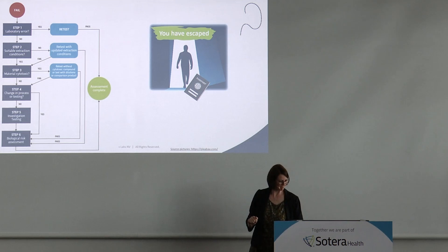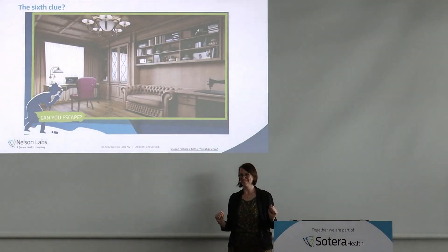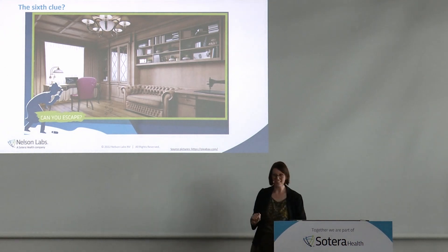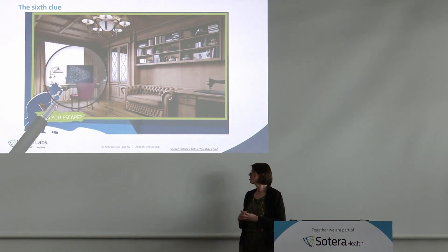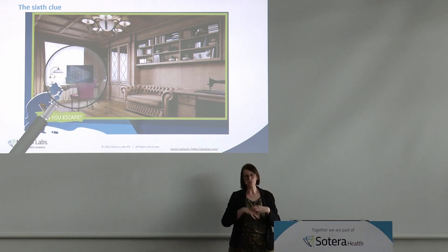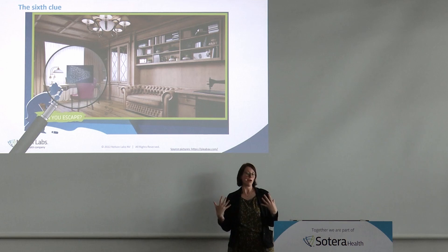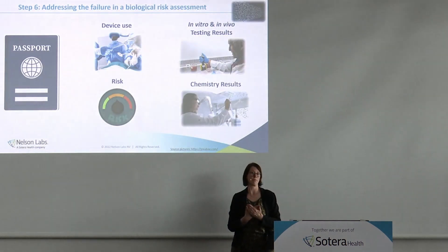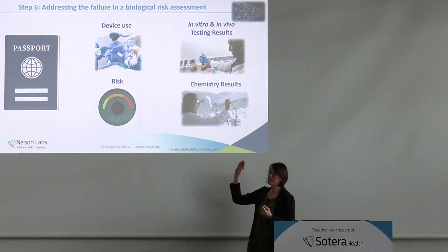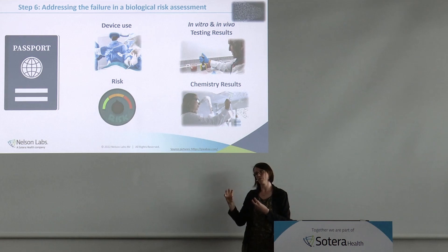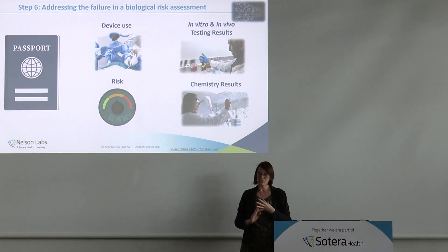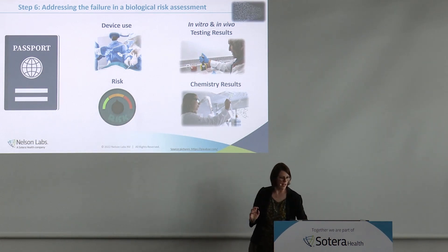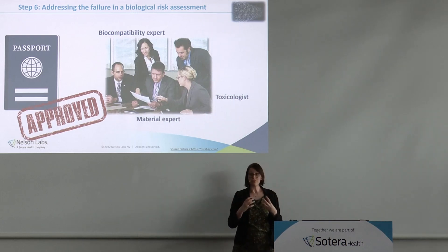The last clue is data on the laptop. At this point you've done investigational testing, looked at all components, done everything possible. There is only one option left: can you create a passport for your device? You have a failure, but based on device use, in vitro and in vivo results — which must be passing; if they're all also failing, that's a different story — and based on risk and chemistry results, you can create a passport. Get it approved with a biocompatibility expert, a toxicologist, and a material expert. That is your way to get out.